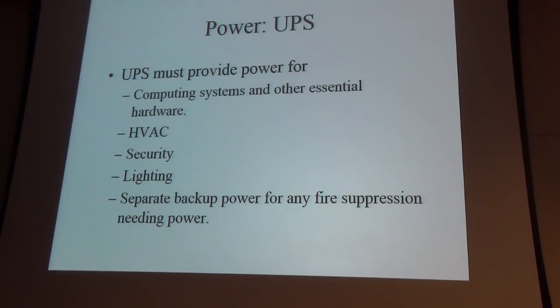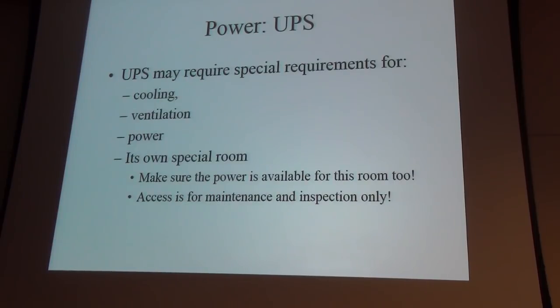If more gear is coming, it must come with a budget to support it. The UPS itself needs a lot of cooling, ventilation, and power. I think it has to do with the batteries — there are fumes, sulfuric acid — so you want venting. The UPS is always in a separate room, never close to servers, network gear, or equipment.